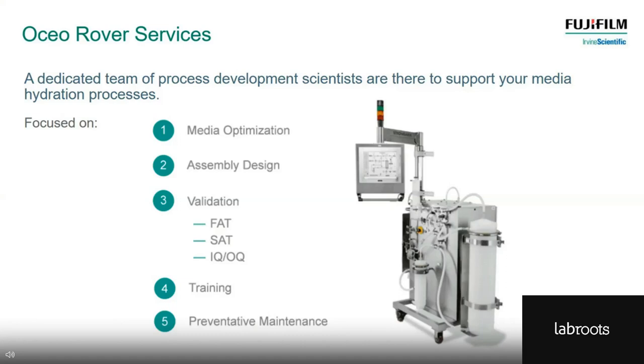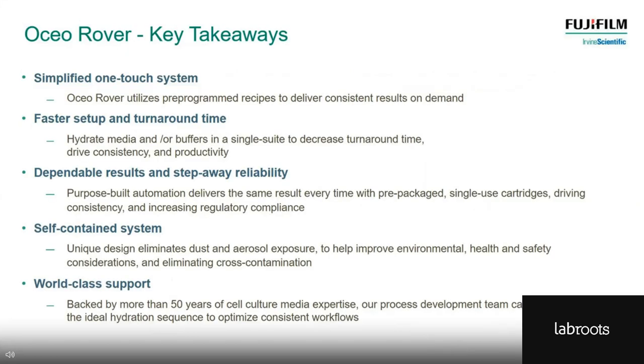Looking back at that media optimization service — I want to emphasize this isn't about getting more product out of the system. It's about using the experience that exists within Fujifilm Irvine Scientific to optimize the way the media components are presented on the skid to ensure correct hydration in a timely and efficient way. When we developed the technology, we had a number of things we were thinking about: how do we simplify the process? We do that by having a control screen that stores recipes, enabling operators to go in, select a recipe, and then pretty much walk away and get the same output time and time again.